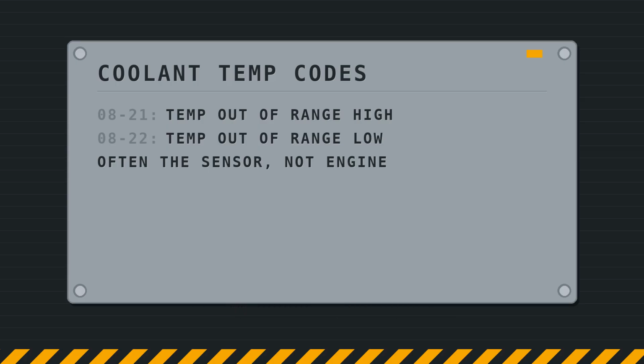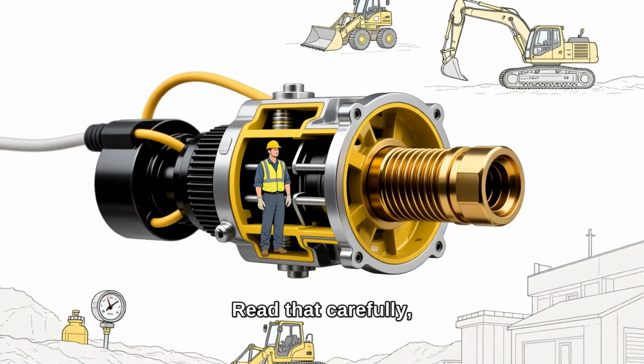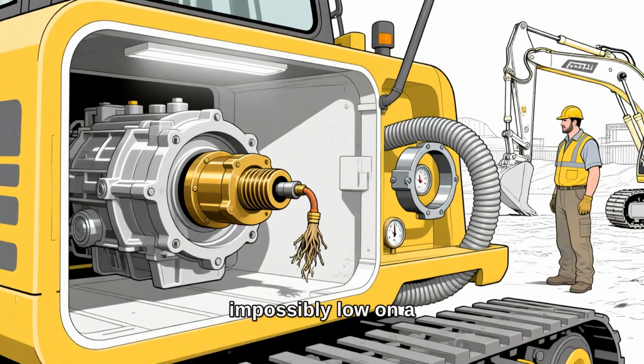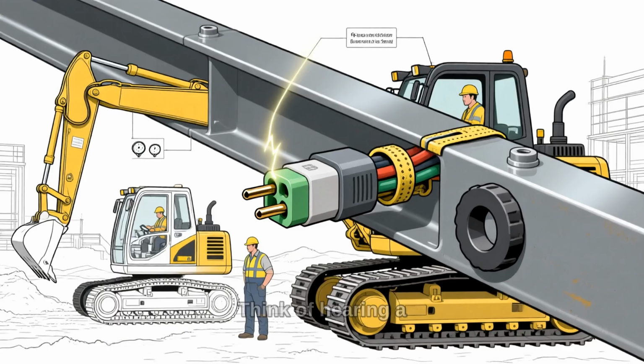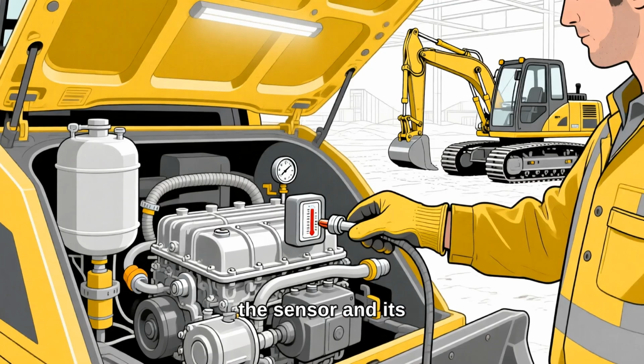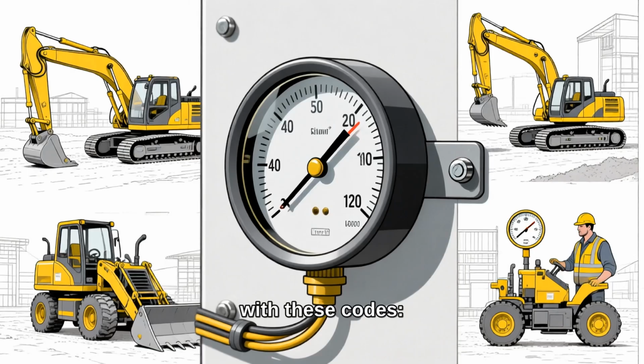Now the temperature codes. Code 821 is engine coolant temperature out of range high. Code 822 is out of range low. Read that carefully. Out of range. That's often the sensor's opinion, not the engine's temperature. That difference saves you money. If the code reads impossibly low on a warm-running engine, the coolant didn't drop. The sensor or wire is lying. Think of hearing a name at a party and losing it 2 seconds later. The signal's there. It just didn't land. So a temp out-of-range code sends you to the sensor and its connector first, long before you touch the engine. That's the whole game with these codes. Separate what the machine measured from what the machine actually is.